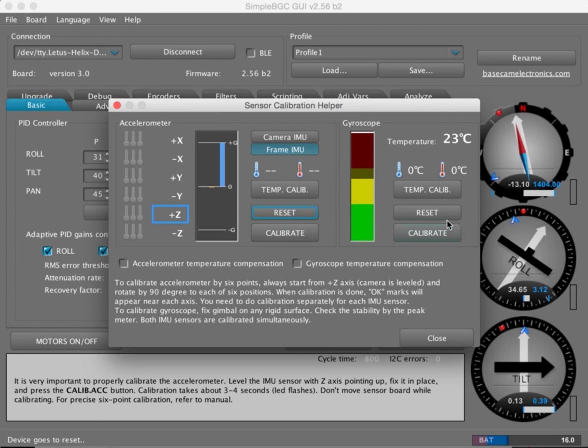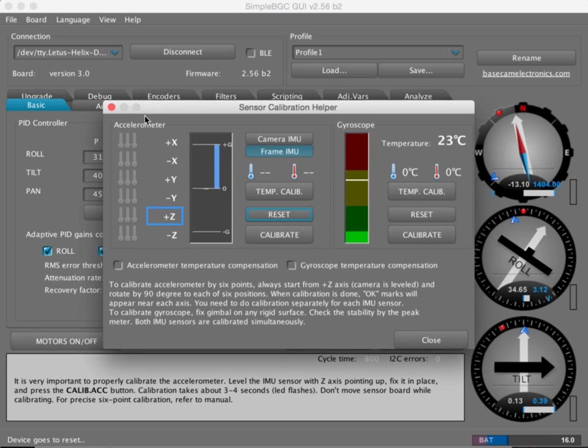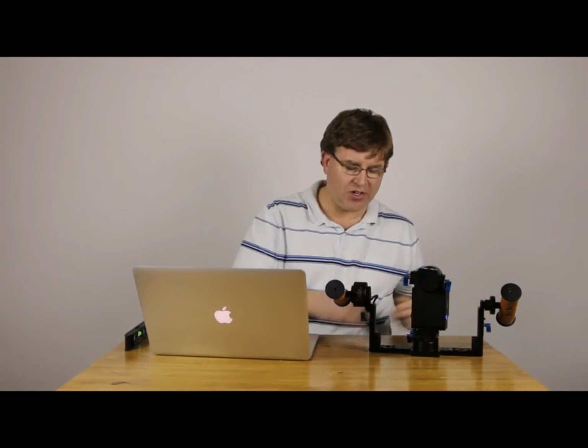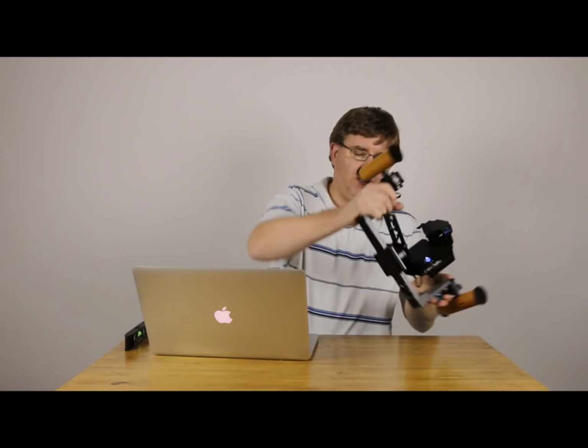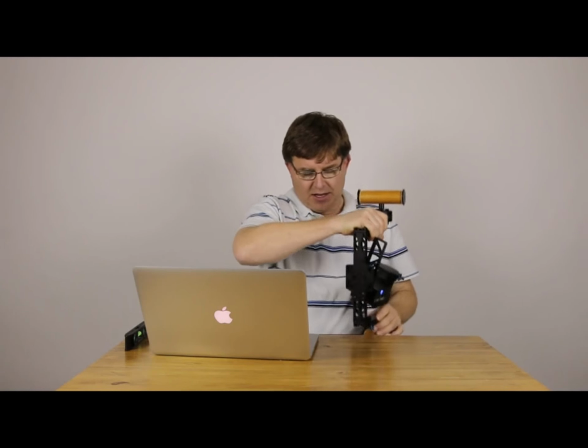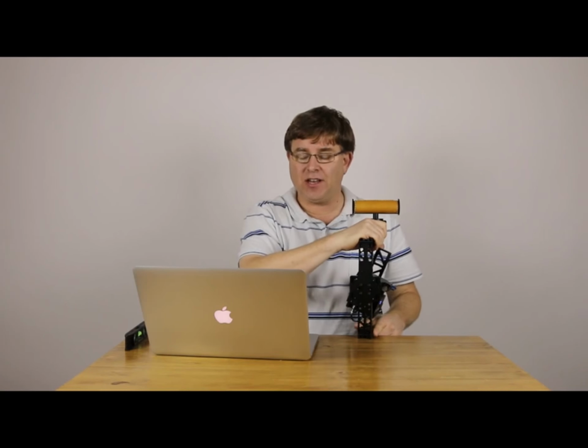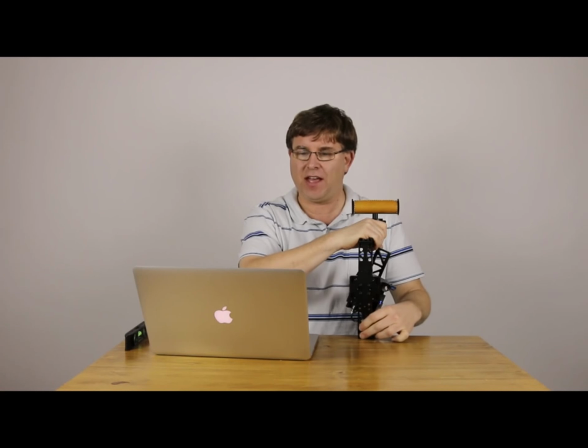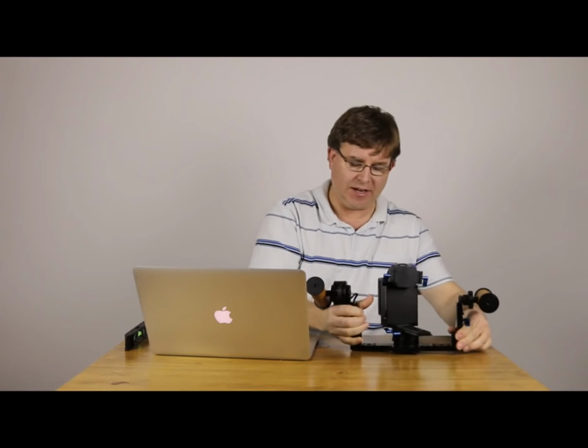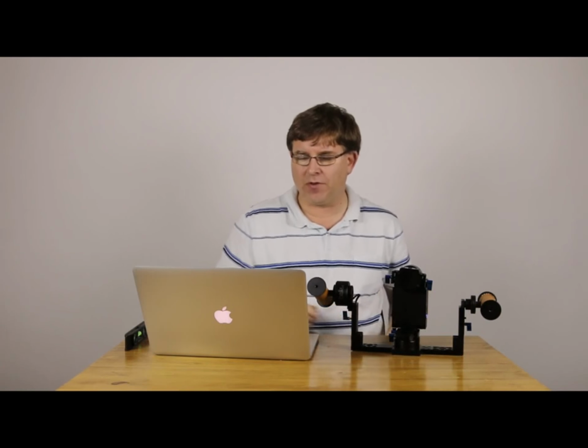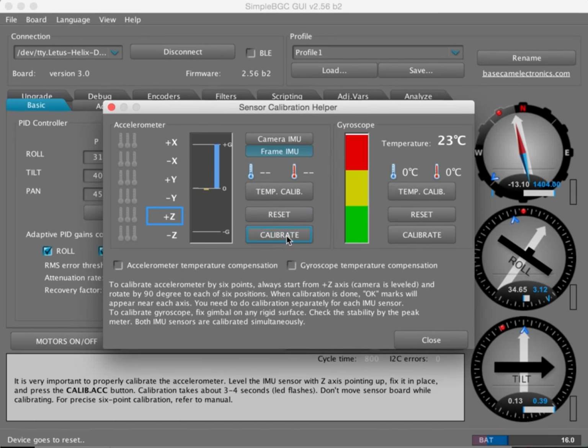On here, this whole box over here is for the gyroscope, and this one over here is for the accelerometer. So I'm going to go ahead and hit calibrate here for the accelerometer. And we don't need any kind of special orientation for this. In fact, many of you who have been using firmware version 2.43b6 might be used to actually having to turn this up like this and rest it here. You do not need to do that. Not only do you not need to do it, but you cannot do that for this version. You have to have it sitting flat on the table for this firmware version, and we'll go ahead and hit calibrate.